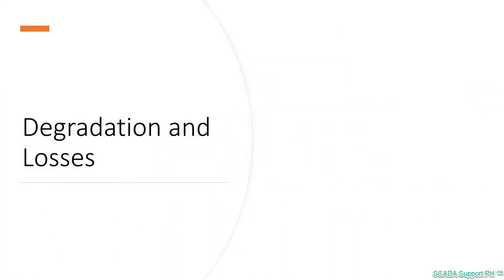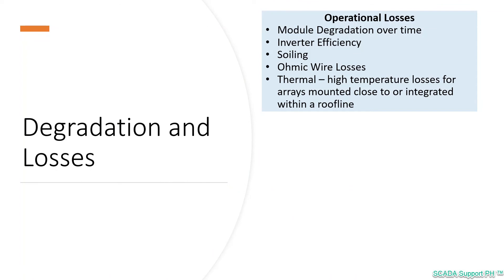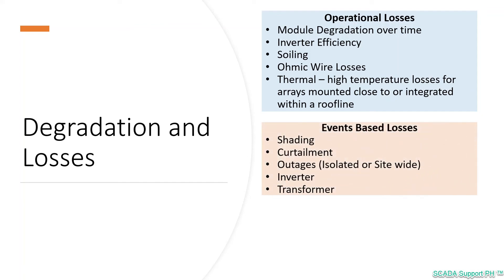However, there are some degradation and losses on a PV system. The actual solar PV system will produce less power during operation due to losses like module degradation, inverter efficiency, soiling, ohmic losses, and thermal losses. We also have event-based losses, which occur on a yearly or seasonal basis, such as shading, curtailment, and isolated outages.